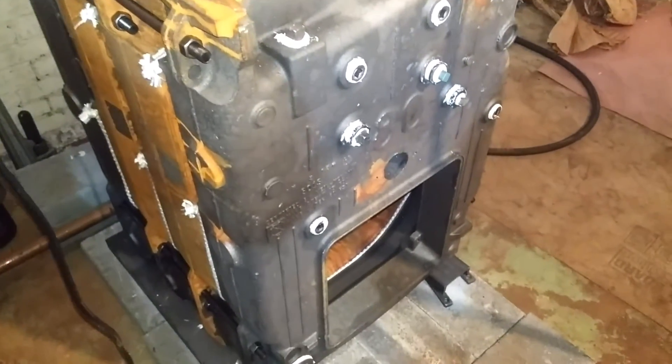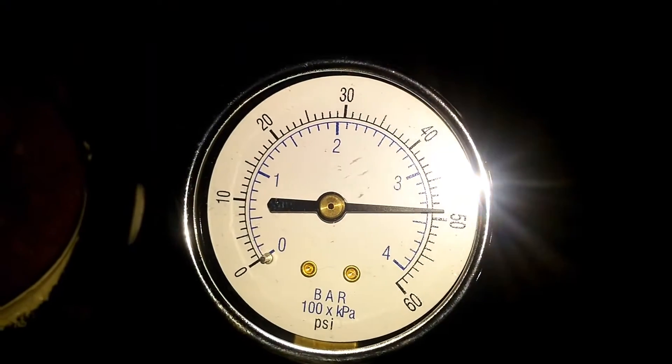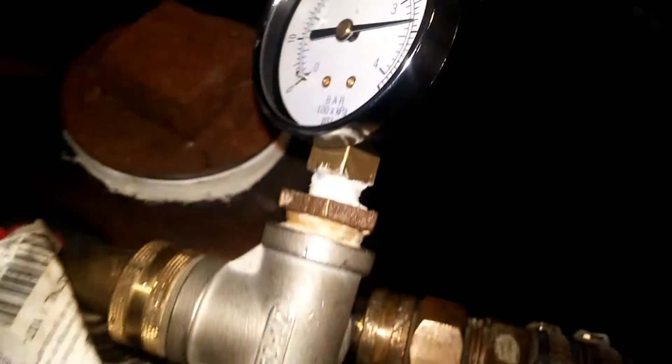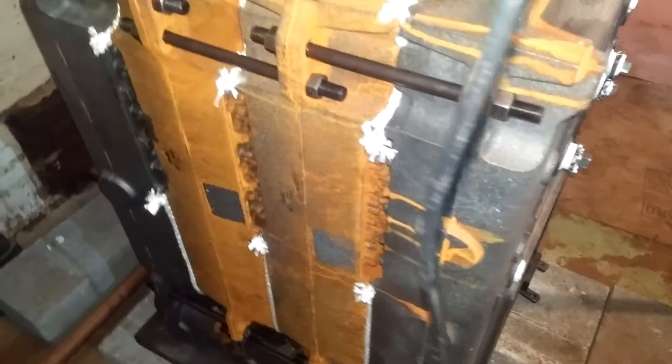Sports fans, it's been 10 minutes and the pressure gauge has not dropped from its high pressure of 49 PSI. The repair that they made at the foundry apparently was satisfactory and there are no other leaks in the seals here and at the rear. So we have a boiler. Yay!